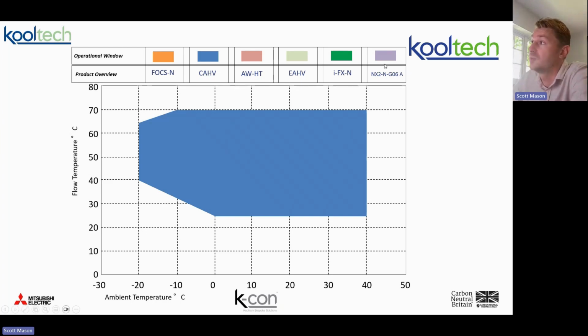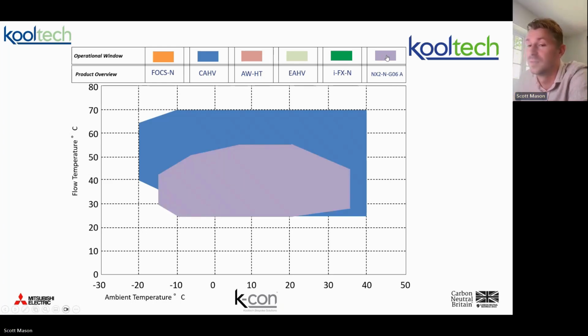The next unit we have in our range, which is our next most popular unit, is actually a Climaveneta product. And Mitsubishi own Climaveneta. The Climaveneta unit is manufactured in Italy by Climaveneta. It's called the NXN or the NX2N. It's basically 2 of the same range, but one of them is larger with a second fridge circuit. And the operating window looks like this. So believe it or not, this is still a robust operating window, but it's a totally different scale of performance. Look, I can give you 55 degrees down to a temperature of +7. So realistically, at your design condition, this is a unit that can produce 50 degrees of heat. So you would need a heating circuit underneath 50 degrees centigrade. If you said it was potable hot water, this would be a preheat only, because I'm not going to be able to give you that 60 that you need.